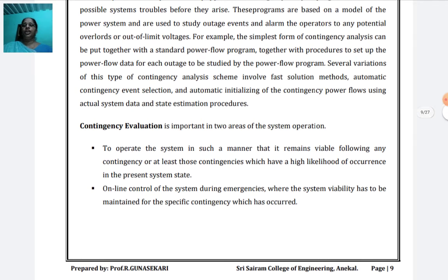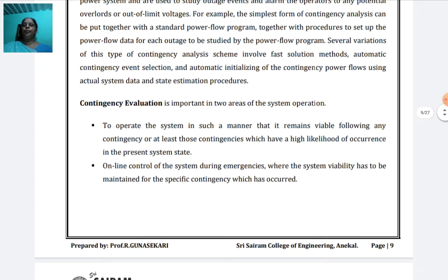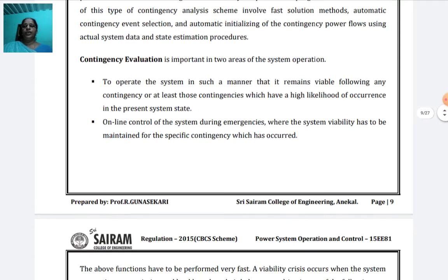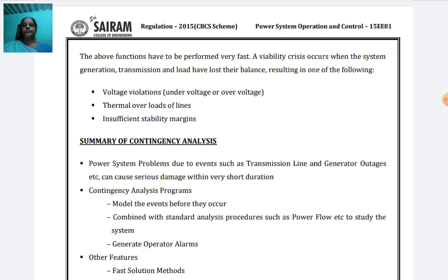Then what is meant by contingency evaluation? There are two important areas in contingency evaluation. One is to operate the system so that it remains viable following any contingency, or at least those contingencies which have a high likelihood of occurrence in the present system state. Second, system viability has to be maintained for the specific contingency which has occurred. This is the contingency evaluation. Now, the power system consists of generation, transmission and load. So what results? First, voltage violations. Voltage violation means under voltage or over voltage. Second is thermal overload of lines. Third is insufficient stability margins.